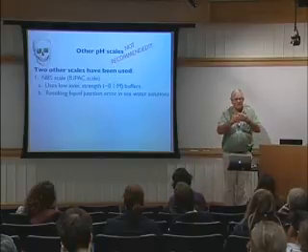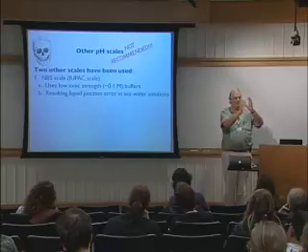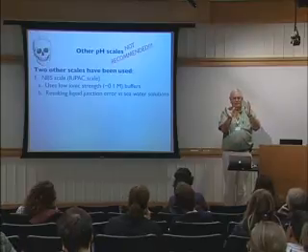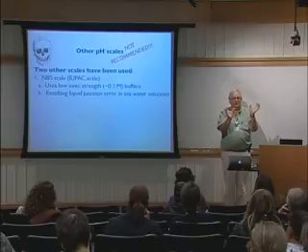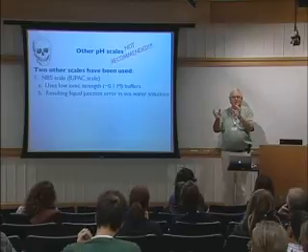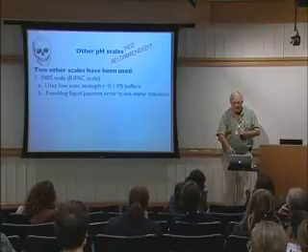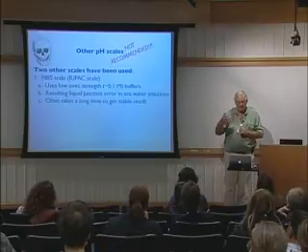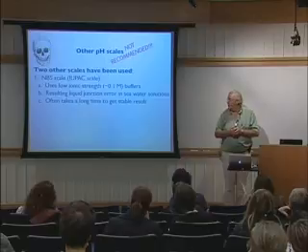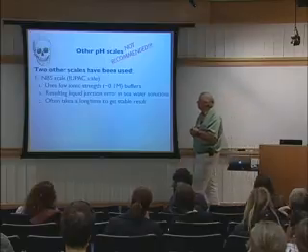Because of this change in liquid junction from a solution where we ended up, and it's a stable diffusion mixture of the buffer and the potassium chloride, we put it in seawater. Now all the ions have got to change and get to another stable configuration. It often can take a long time to get stable results. And that's a problem.